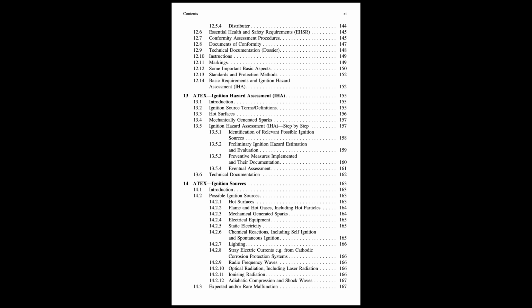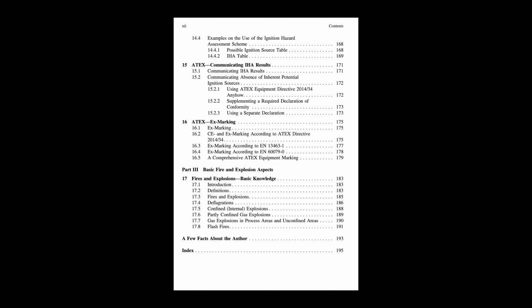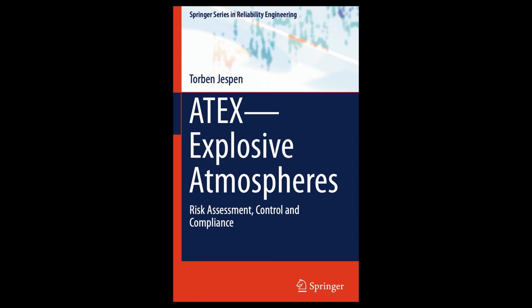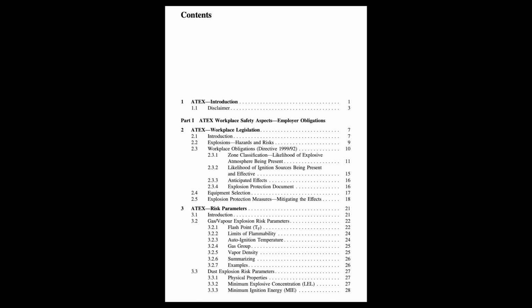Got it. Then we have gas groups, IIA, IIB, and IIC. What determines these groupings? These groups categorize gases and vapors based on how easily they can be ignited, specifically by sparks or flames. It relates to their minimum ignition energy, MIE, or something called the maximum experimental safe gap, MESG. Okay, simpler terms. Think of it like this. Some gases need only a tiny spark to ignite, while others need a much bigger one. Group IIC contains the most easily ignited gases, like hydrogen and acetylene. They need the least energy. So they require the highest level of protection. Exactly. Equipment rated for IIC offers the most stringent protection against spark ignition. Then comes IIB, like ethylene, and finally IIA, like propane or methane, which are relatively harder to ignite by spark.